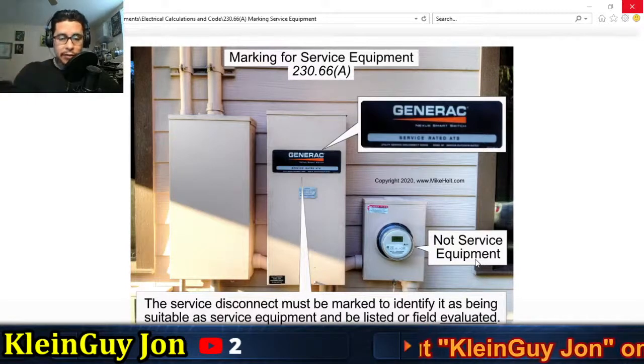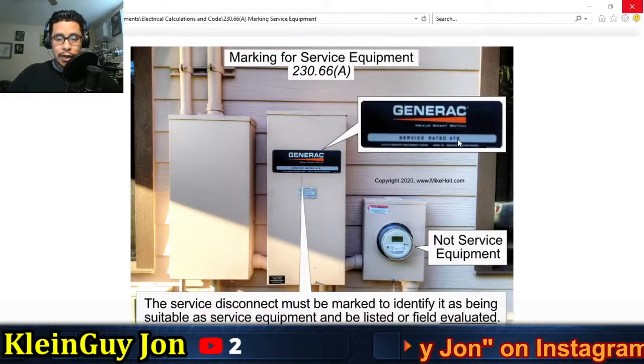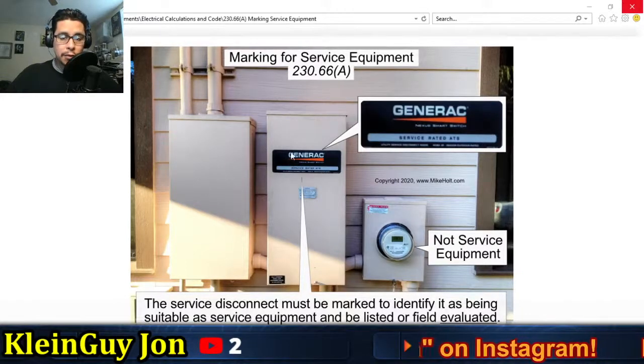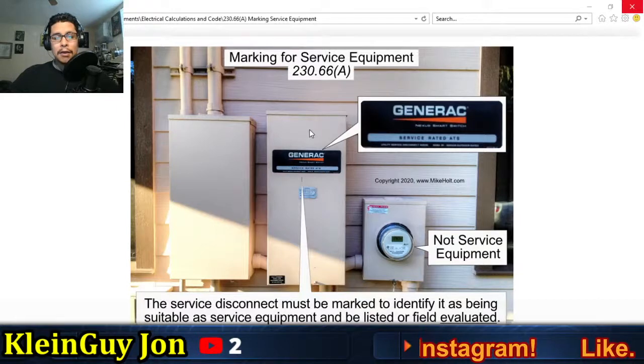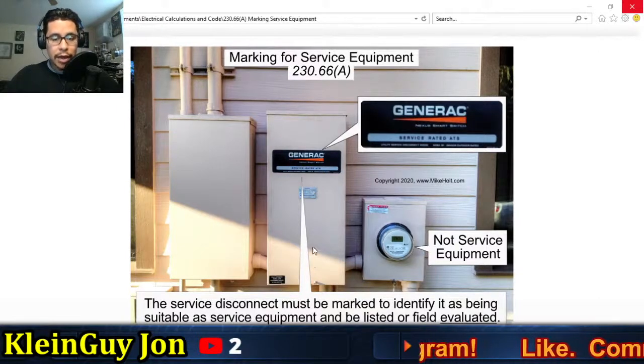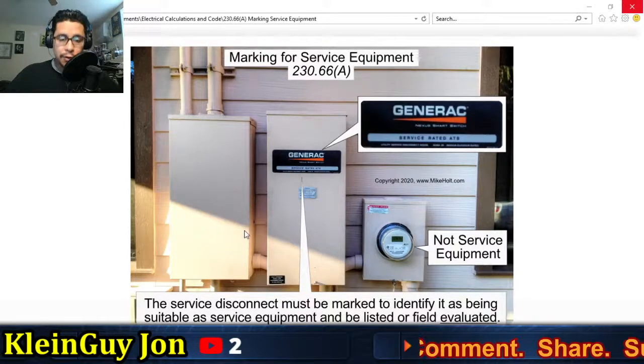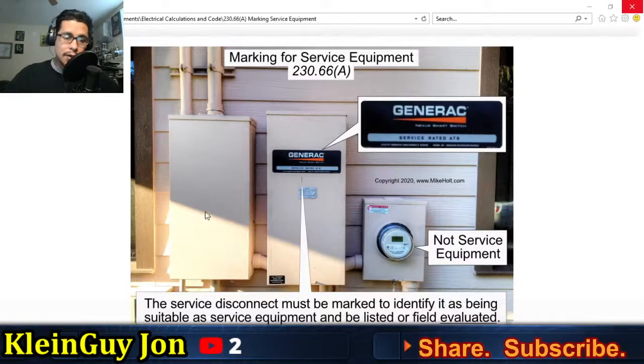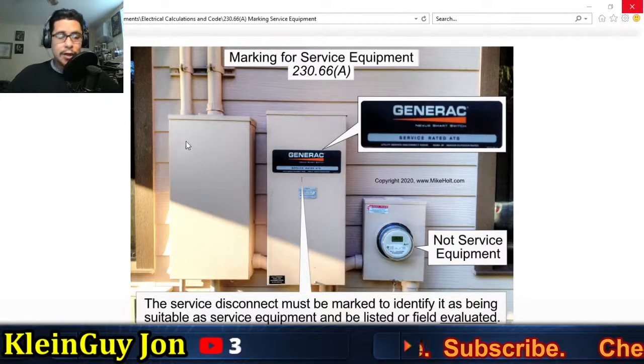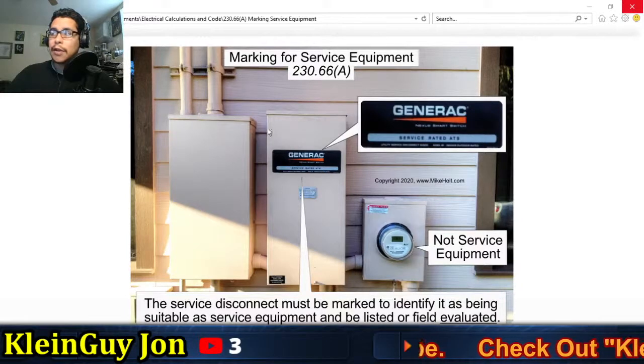It's the only way they can bill you. The disconnect, as you can see here in the graphic, it says Generac, service-rated ATS, automatic transfer switch. This is for emergency power, that is what's known as a service. You can disconnect, reconnect. You have your regular service disconnect, which is also attached to the meter that feeds the disconnect, either fused or non-fused. It is known as a service. These two are considered a service. Not this, not service equipment.